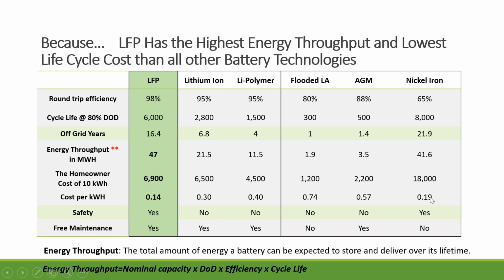Nickel iron is about number 2, at around 41.6 megawatt hours, and the other ones are substantially less. Now, if you take the out-of-pocket cost and divide it by the energy throughput, you get the cost per kilowatt hour. You can see that the LFP chemistry that we offer delivers at 14 cents per kilowatt hour, and AGMs are substantially more, 3 or 4 times more. So this is how you do an apples-to-apples comparison. At the end of the day, energy cost is calculated by how many cents per kilowatt hour.